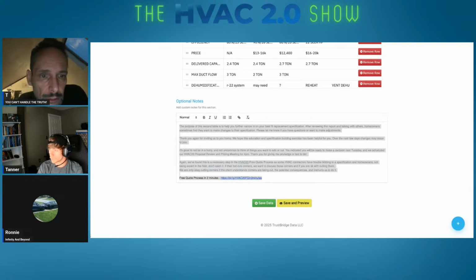The cooling likely load module is key to making good replacement sizing decisions. Cooling likely load, green, is 1 to 2 tons, with duct capacity max at 2.4 tons. Depending on your equipment choice, we suggest not going larger than 2-ton single stage, 2.5-ton 2-stage, or 3-ton communicating variable speed.